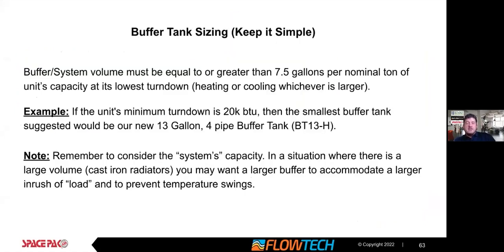Buffer sizing for design criteria. In the old, not in the old days, but previously, the purpose of a buffer tank is really to reduce short cycling of your equipment. The inverter monoblocks and the inverter compressors that we have on the heat pumps now, they will ramp themselves down to match the load. So if there's a 50% load on the structure, the unit's going to ramp down to 50%. The impact of that on buffer tanks is that we can get away with a little bit smaller sizing on the buffer tanks. And one reason that SpacePak has brought out their 13-gallon buffer tank, which is suitable for even a 5-ton heat pump, as an option for purchasing.